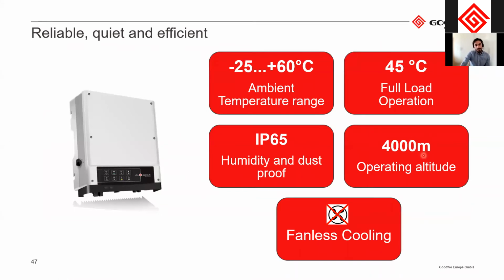Here are a few key points for our storage inverters. They have a slightly smaller temperature range than the C&I inverters, but from -25 up to +60 degrees Celsius. They can operate at full load up to 45 degrees Celsius. Most of them, as I said, apart from the combined solution, the ESA inverter tower, have an IP rating of 65 and can therefore be installed outside.